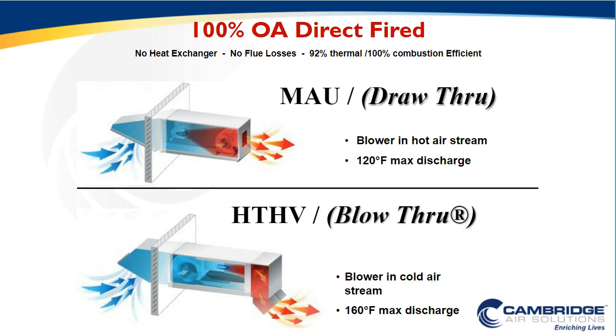This technology we're talking about today, which is the HTHV, is similar in design to the draw-through makeup air with one key design difference, but a massive performance difference. What HTHV does, by moving the blower in front of the burner, where our mechanical devices are now in the cold air stream, is achieve that performance spec by dialing up the discharge temperature, dialing up the temperature rise, such that we can now achieve a 160-degree discharge in a small box. We can achieve a higher temperature rise and a higher leaving air temperature without compromising any of our mechanical equipment, any of our belts, any of our bearings, or any of our motors. So it allows for a higher capacity in a smaller volume. And we'll go into more depth in the energy efficiency side about why this is impactful from a low energy footprint. But first, let's talk about safety.